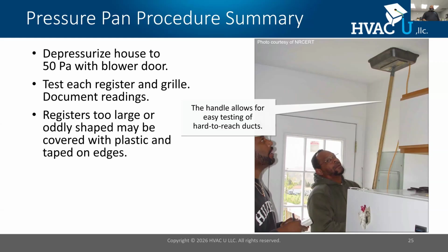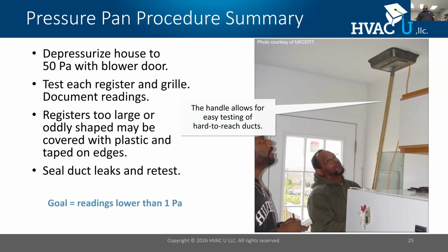All right, and what you're going to do, you're going to test each register and document the readings. Since this is a pressure test, if you have registers that are too large or oddly shaped, you can cover them with tape or plastic and get your reading that way. And how you fix it, you're going to seal the ducts and you're going to reperform the test. Okay. And the goal is to have pretty close to zero. I want less than one. Anything over one is really unacceptable leakage. You're having leakage, conditioned air leak out of the thermal pressure boundary. Again, that is a bigger energy penalty. All right.